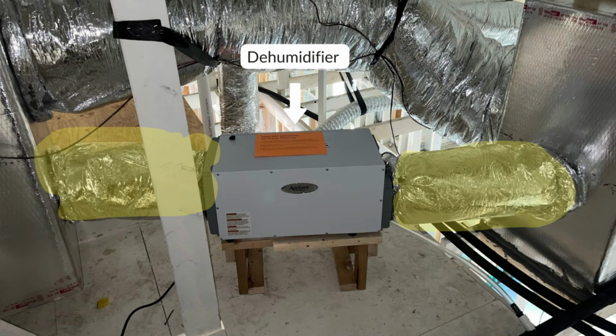The first way to install a dehumidifier on a horizontal furnace is to tie a new duct run onto the existing return ductwork on your central AC system, then attach it to the dehumidifier. Then we'd run a second duct from the dehumidifier to the return plenum of your central AC.